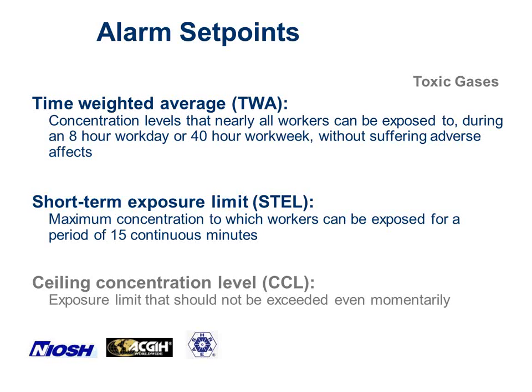I want to turn on exhaust fans. I want to open up ventilation dampers. I want to do things like that. When I get to the STEL, I want to alarm you and tell you to get out. When I get to CCL, it doesn't matter—it's already too late from a controls perspective. That limit is defined in these standards, but there's nothing I can do from a control standpoint. It's already too late; the first two things didn't work for you.